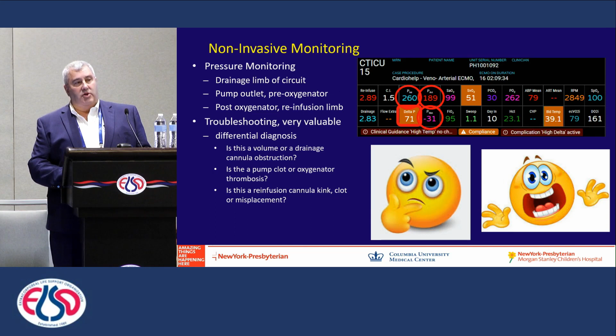Well, if we look at the reinfusion pressure going back into the arterial cannula, we see that's only 189. So that's actually a reasonable pressure at 3 liters of flow with the current circuit that we use. So we look a little further into the delta pressure, and the pressure drop for 3 liters of flow across this oxygenator, that 71 is really high, and it lets us know we're about to do an oxygenator exchange. So these are the ways that we use non-invasive things like pressure monitoring to help us determine when we're going to need to act before we get into trouble.